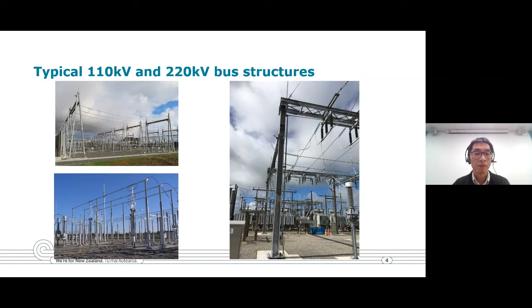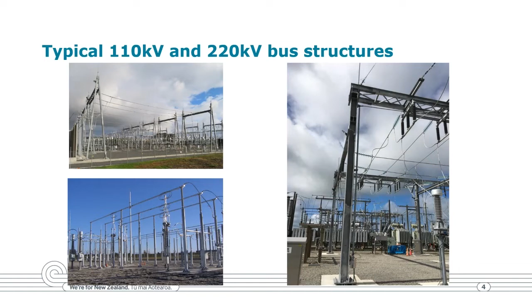The modern design of the 220 kV rigid bus uses an A-frame gantry and steel post, and aluminium bus bar for the rigid bus system, whereas for 110 kV we're using the I-beam as the gantry structure rather than lattice gantries.